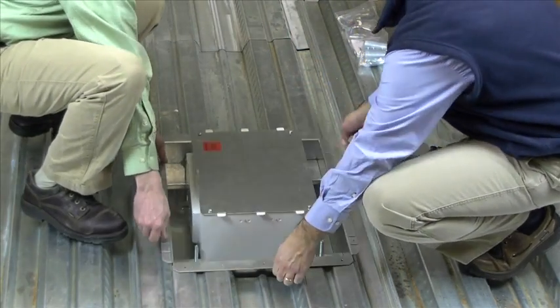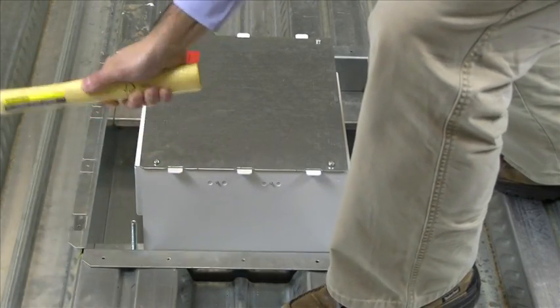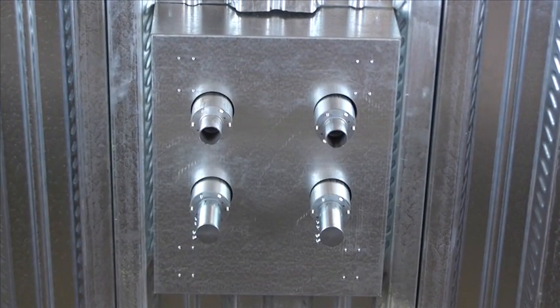Now that your box has been positioned into the opening, secure the box assembly to the decking by hammering down the screw tabs and fasten to the deck with Tek screws as shown. The box can also be secured in place by seam welding.